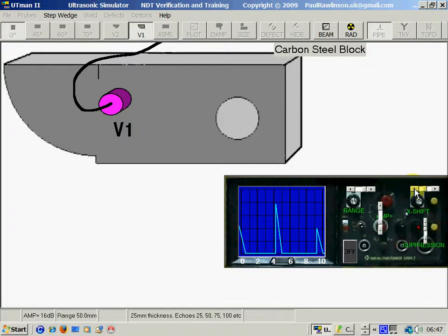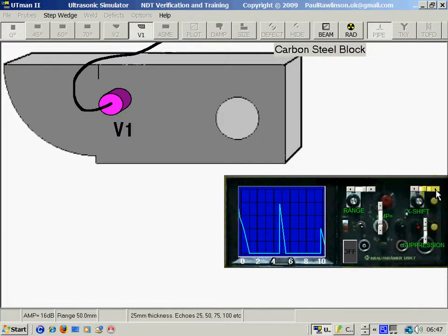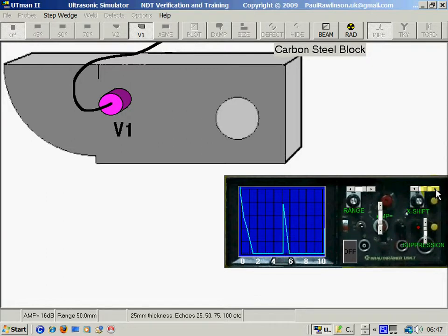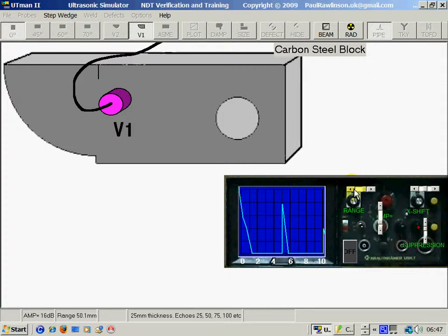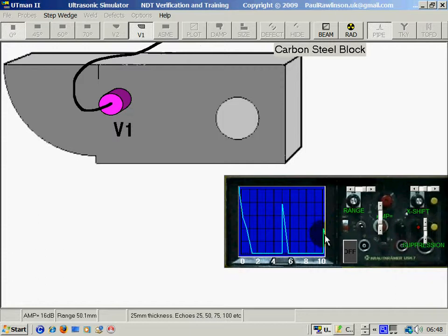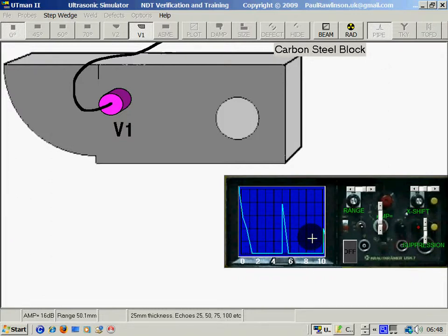Using the range and the X-shift we can position the echoes so we have our first one in the center of the screen representing 25mm and the second one representing 50mm. The full screen now represents 50mm.